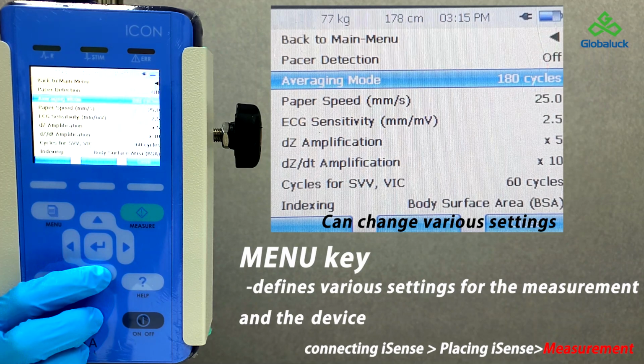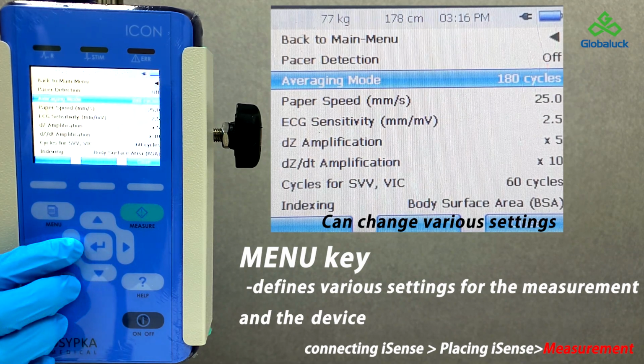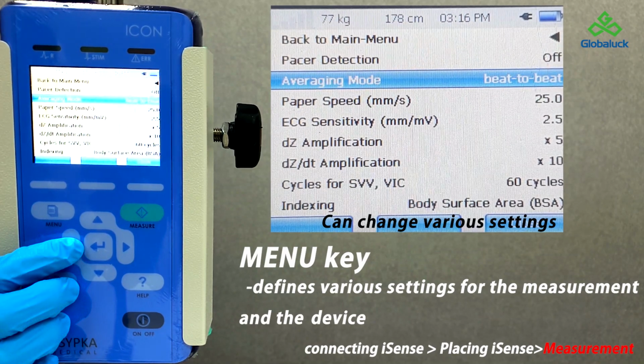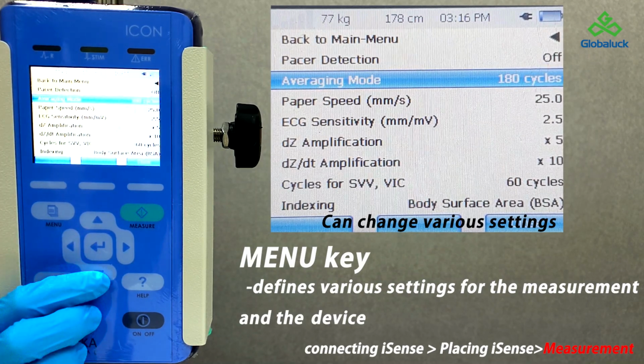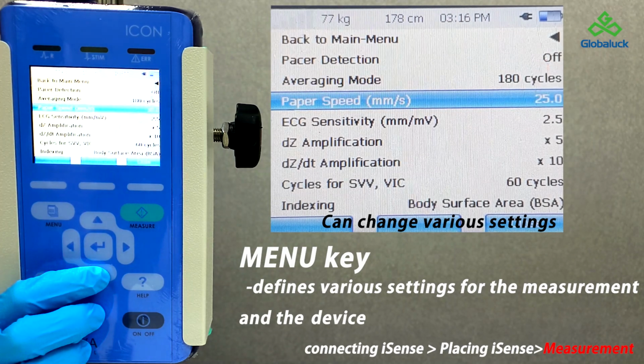Icon determines hemodynamic parameter values beat to beat, while the results are displayed as the mean results averaged over a number of cardiac cycles. Using the horizontal arrow keys, the number of cardiac cycles for averaging can be set from beat to 180. Normally, it is recommended that the values are averaged over 30 or 60 cardiac cycles, thus providing less fluctuating results. Paper speed is the velocity with which the waveforms are written onto the display.